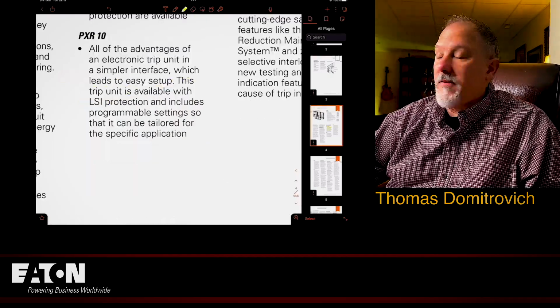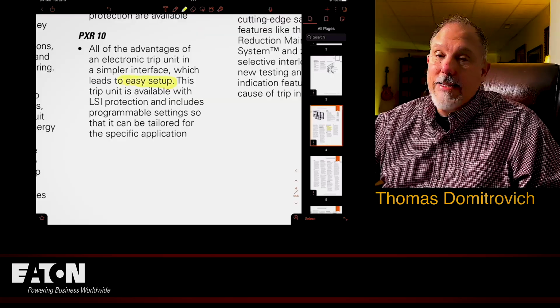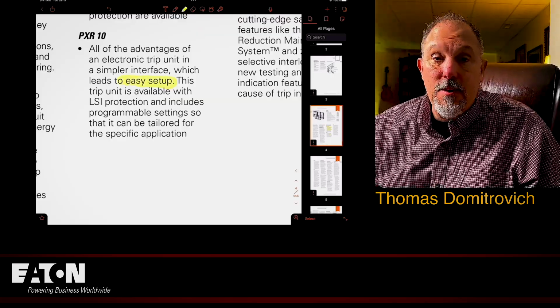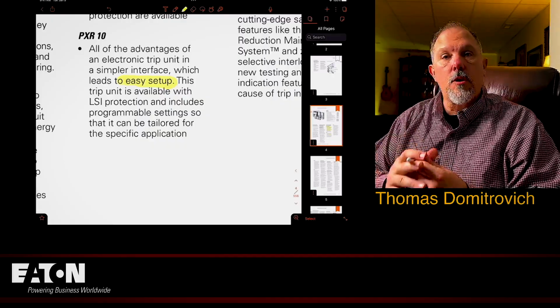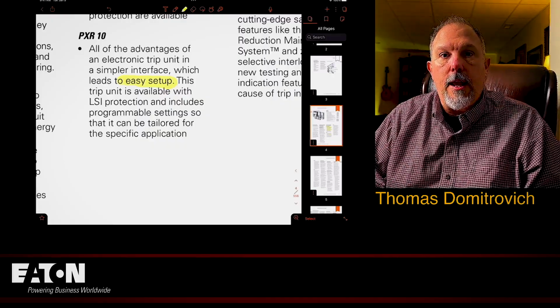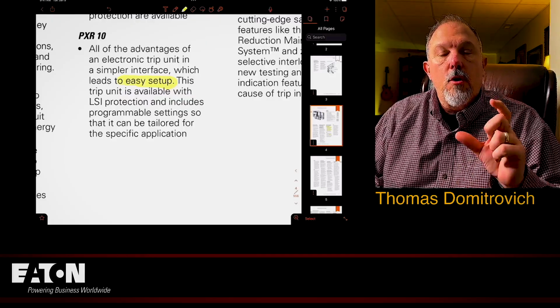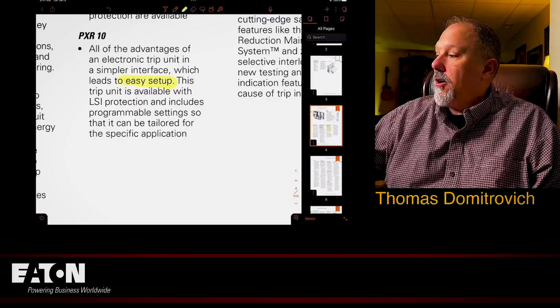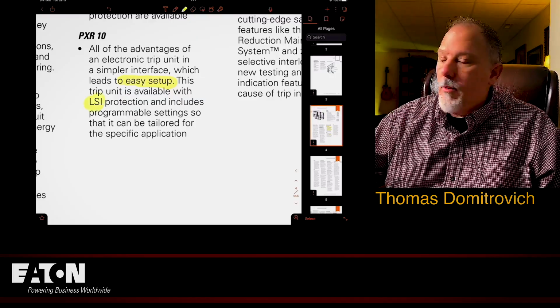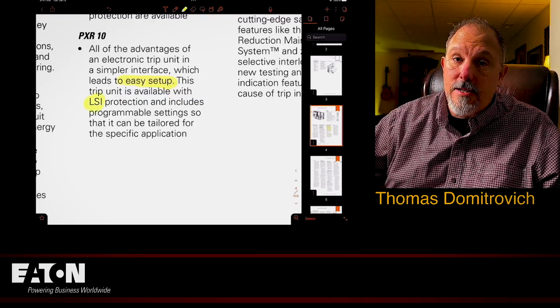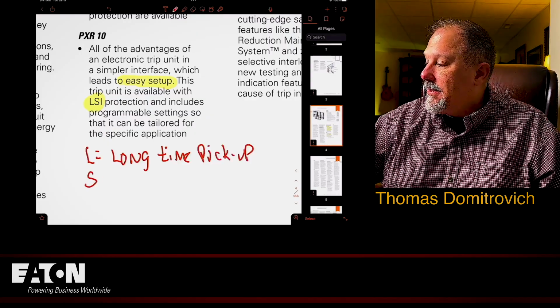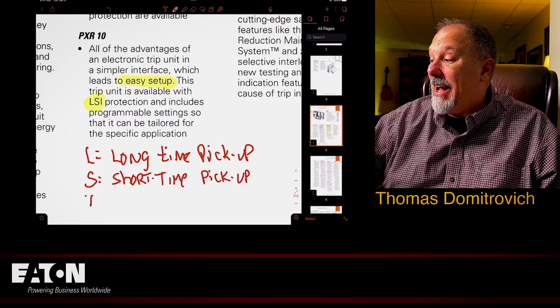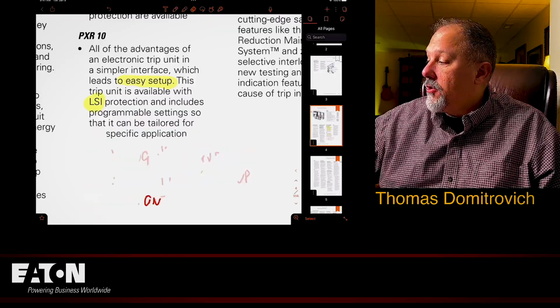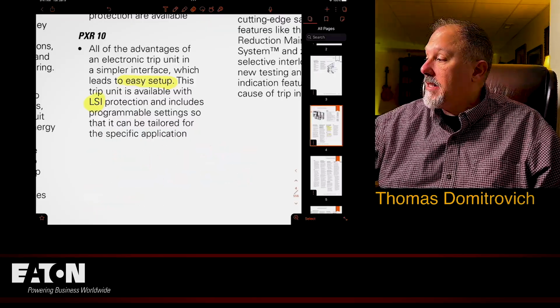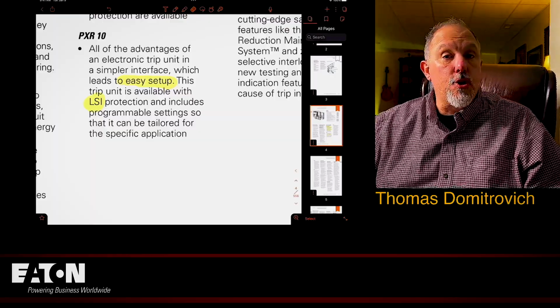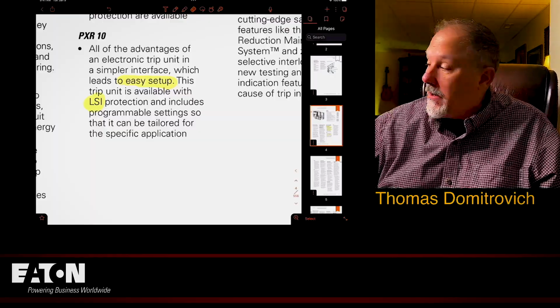PXR10, all of the advantages of an electronic trip unit, and they focus on easy setup. And when someone says, hey, this is easy setup, you know what that means? Minimal functionality. The more functions you put on a circuit breaker or a trip unit, the more complicated the device is going to become. Now, you'll notice here it says LSI. What is LSI? L is for long time pickup, S is short time pickup, and I is instantaneous. You'll sometimes see LTPU for long time pickup, STPU for short time pickup, and then INST for instantaneous.